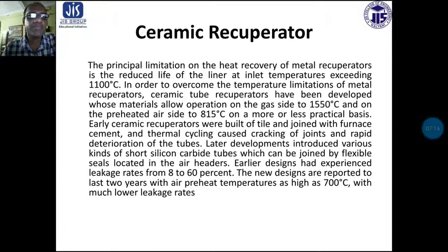Early ceramic recuperators were built of tile and joined with furnace cement, and thermal cycling caused cracking of joints and rapid deterioration of the tubes. Later developments introduced various kinds of short silicon carbide tubes which can be joined by flexible seals located at the air headers.